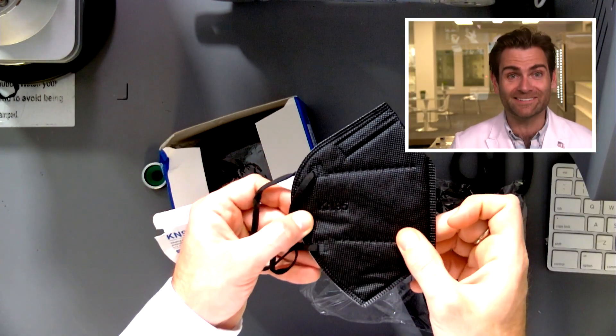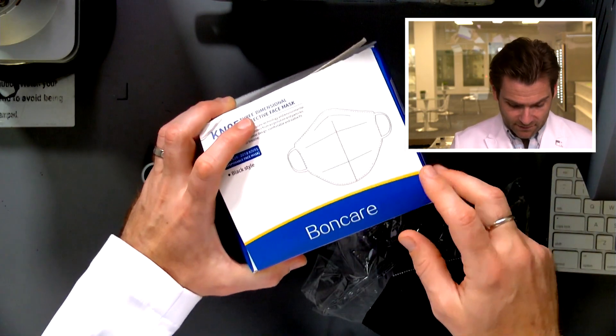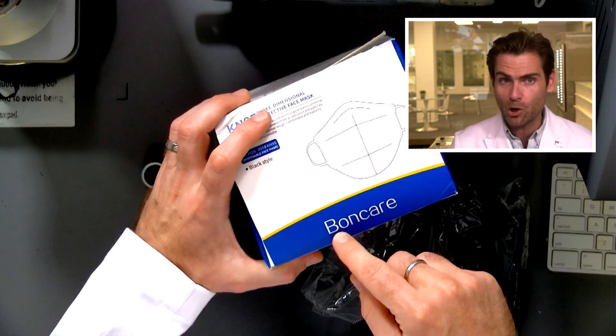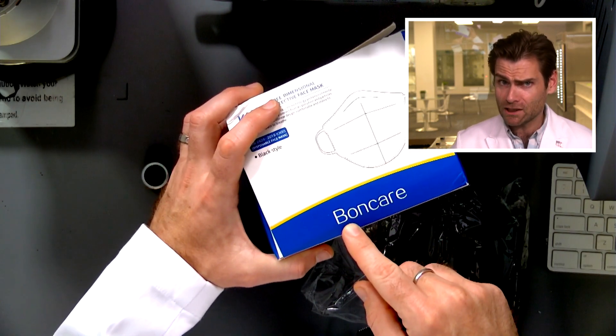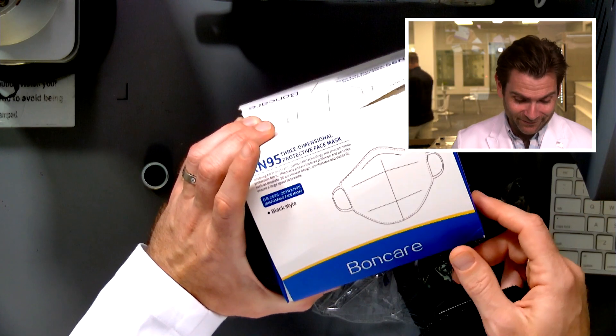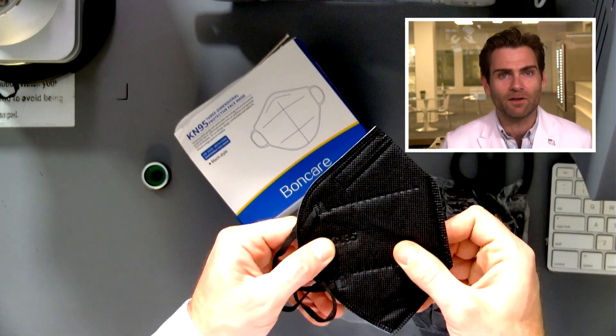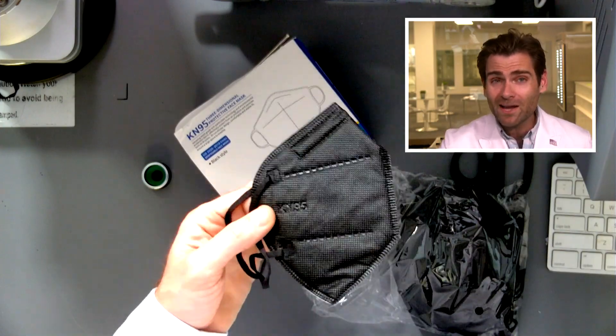Now it could be that they just ran out of characters — that's a long name — but I think what's more likely is that they were really in love with 'Boncare' and didn't want to ruin that effect on the mask. Either way, it's against the standard. And when I find that people are not meeting the standard for something simple like putting their name on the mask, they oftentimes don't meet the standard when it comes to the machine test.